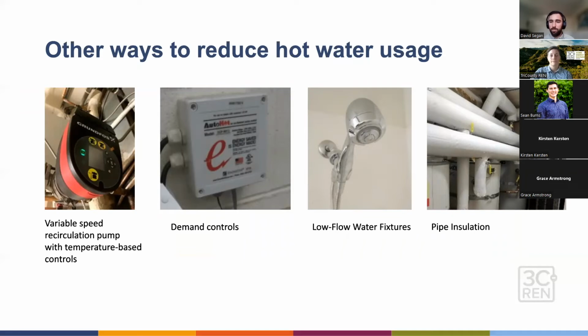Here are some other measures that can contribute to reducing that big chunk of the pie that the domestic hot water system uses. In many multifamily buildings, there's a recirculation loop, so you constantly have hot water going around the building, so you don't waste water waiting for it to get hot. Normally that loop is on a high speed, the pump's working at full capacity, and we can reduce that to only when it's needed with these first two measures. So you still have the hot water ready to be used, but it's not using as much electricity to pump it around.